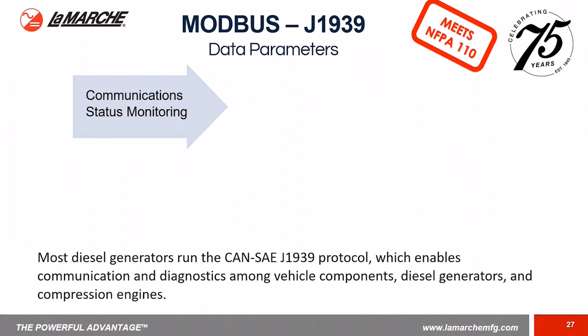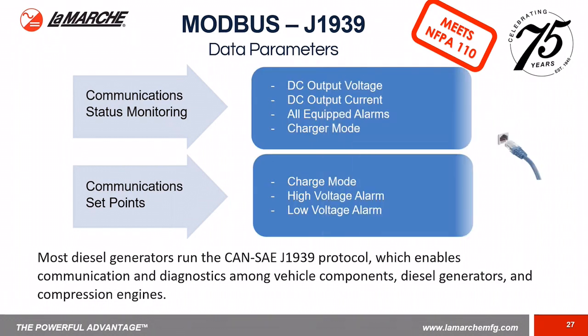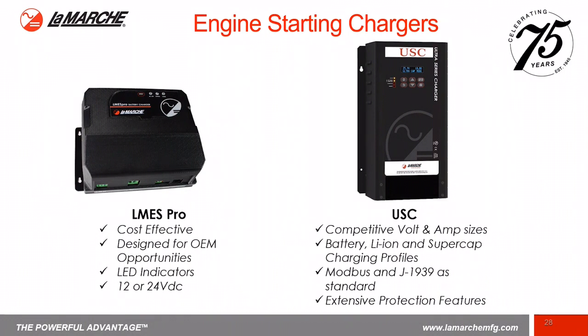Modbus and J1939 provide communication status monitoring for DC output voltage, DC output current, all alarms that may be present, and the charger mode. You can also remotely set the charge mode, load equalize, or even adjust the alarms. And that's why the LMES Pro and the USC are a preferred charging source solution for the supercaps, along with NiCad and lead acids also.